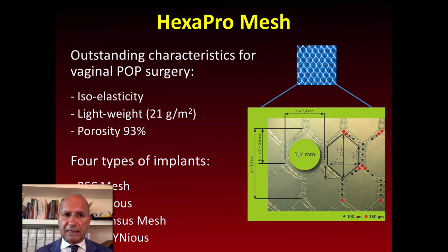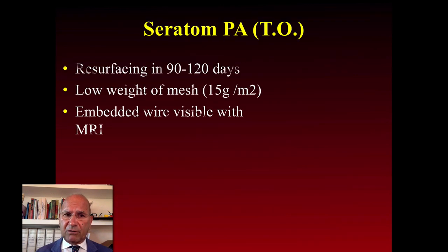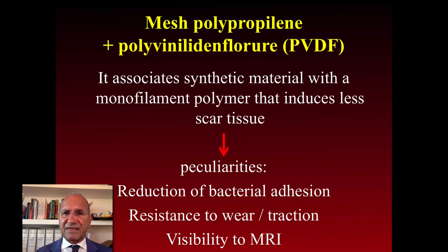These are some new proposals: the hexagon mesh with lightweight — 21 grams per square meter — with high porosity. There is also the titanized mesh implant, which with this new material reduces inflammation rates, has no encapsulation, and shows low shrinkage. Other proposals include an embedded wire visible with MRI to increase visibility of materials once implanted, and PVDF with the peculiarity of reduction of bacterial adhesion and resistance to wear or traction.